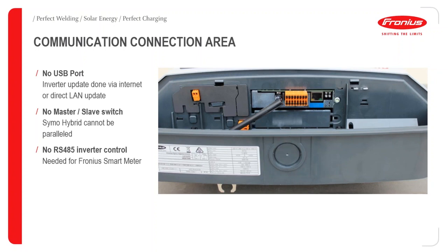So the Symo Hybrid has a different software running in the inverter compared to the other units, and that's why it doesn't get done via USB. All of the update gets done via the internet, as you would do a Datamanager update. You'll also notice that there's no master-slave switch on there. That's because only one hybrid can be in the system at one time, because the hybrid inverter is part of an RS485 communication loop, and the inverter is the master in that, and in an RS485 loop you can only have one master.